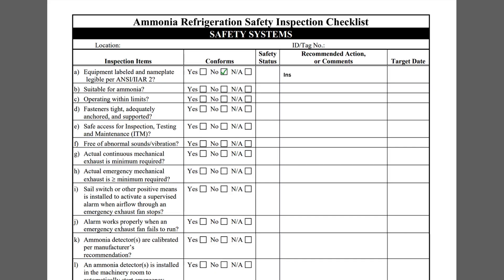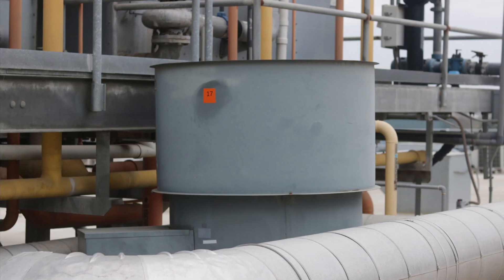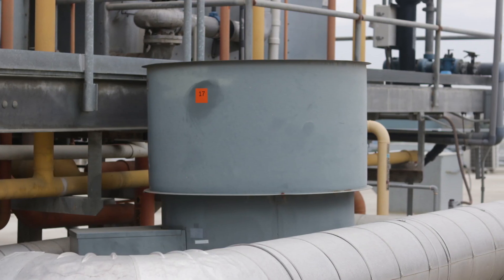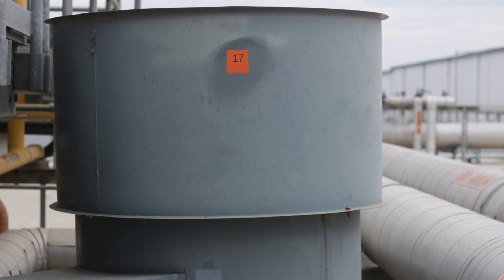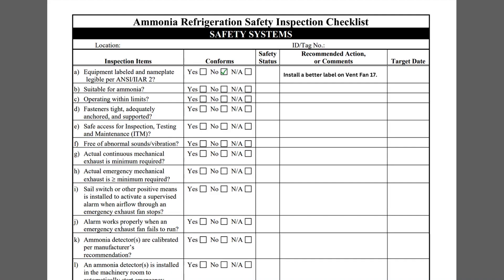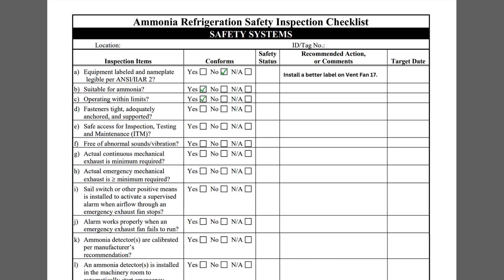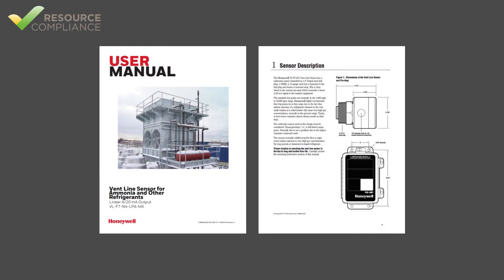Item A asks if the equipment is labeled and has a legible nameplate. A proper label consists of the component name and ID number. Since this label only has an ID number, it should be recommended that it be relabeled Emergency Ventilation Fan 17.